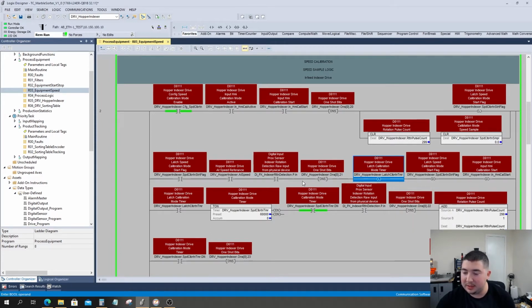Once we see all these conditions, we'll go ahead and latch the sequence start command, which will begin sampling the speed. To get a good sample, we're going to run the sequence for a full minute. Since the speed is based in RPM, it just seemed like an easy thing to do. So we'll just run it for a full minute, and it will give us our speed command.